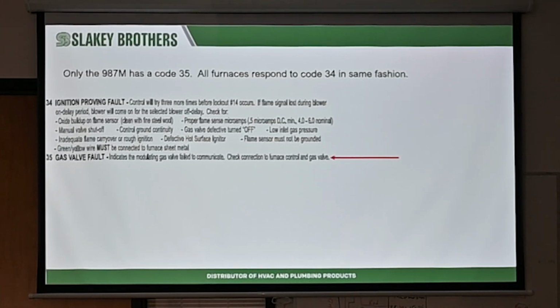In the many years that I've been doing this, I've replaced one flame sensor. One. That's it. 17 years, I found one flame sensor I replaced. And it was still working. It was on a propane unit, and for whatever reason, the propane creates some kind of little chemical reaction with the atmosphere. It was eating away at the flame sensor. Where I'm getting at here is, very rarely, when you got a system that's not sensing a flame, and you can see a flame come on, and you can see the flame hitting that flame sensor, I've never had a faulty flame sensor. I get a lot of people call me and say, hey, I already replaced the flame sensor and I still get a flame fault. Well, it's probably not your flame sensor then.